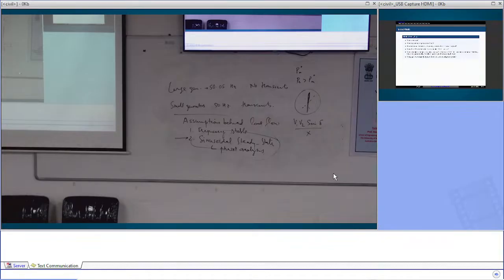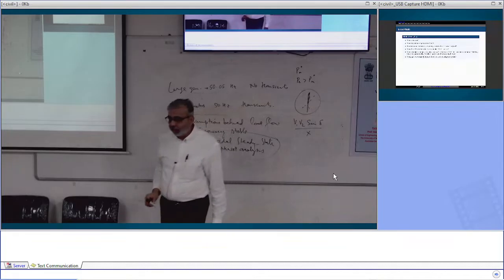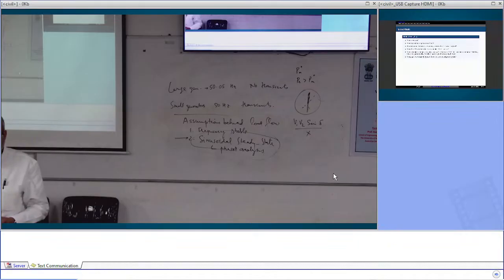So what are we modeling? We are modeling how generators oscillate and they dump power in each other. And oscillation is primarily because of the large mechanical inertia of the generator. Right? अगर उसमें जनरेटर में inertia नहीं होता तो जैसे वो यहां आता लॉक हो जाता एकदम. As soon as it came there, it could lock, but it can't lock because it has got a huge inertia. वो चल पड़ा है. It has to go that way, then that way, धीरे धीरे करके वो आकर आपको फिर लाइन पे लगेगा. And in the meantime, it has caused problems to so many other generators.